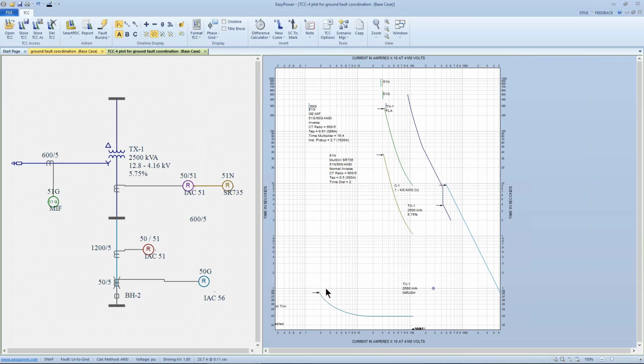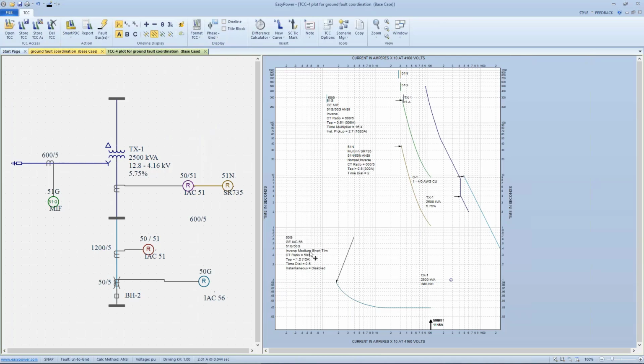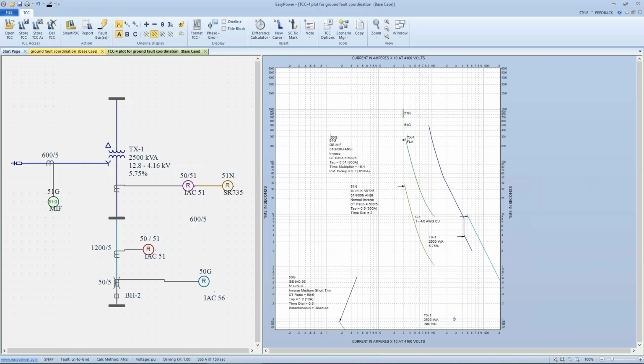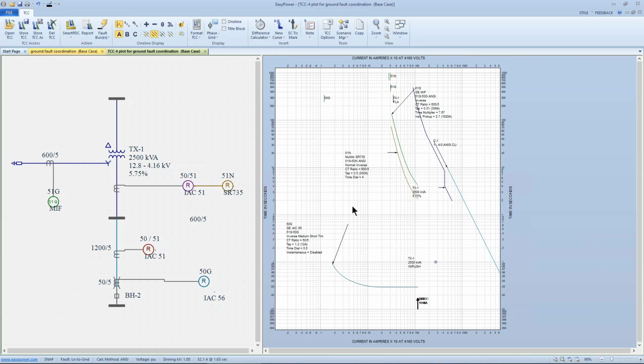All right, so here's our 50G down here, ready to detect relatively low levels of zero sequence current. And again, how much we want to tolerate is the minimum point set here. To coordinate these with the same pickup rating, we need to adjust the time dial, and in essence make them parallel as much as possible. And at this point, we see some coordination with the 51N tripping first at this level, and then the ground current sensor tripping at that level. So at this point, we've got the protection coordination verified.